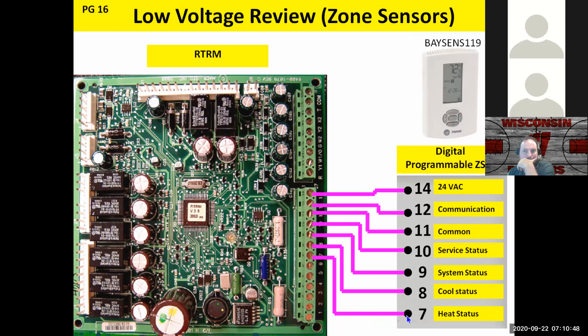So, 11 is your common, 7 is a heat status, 8 is your cool status, 9 is your system, 10 is your service. The number 14 wire is there just to make the display work on the control. So basically this thermostat works on 11 and 12, which is your common and your communication. And again, this is an all 32-volt DC circuit. If you see anything wired on these 7 through 14, that's what you're working with. You're working with this kind of control and a DC circuit.